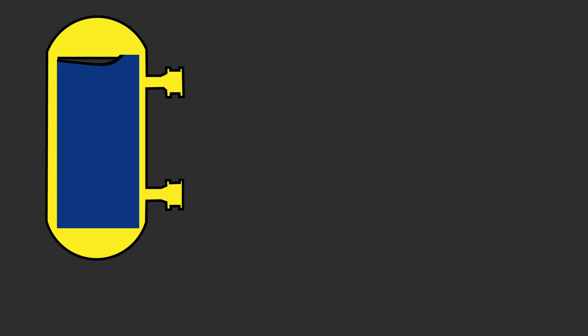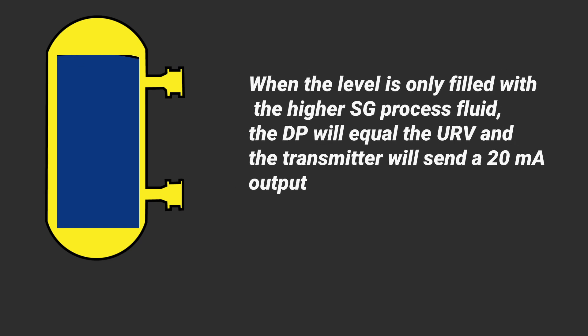Rule number three, when the level is only filled with the higher specific gravity process fluid, the DP or the differential pressure will equal the URV and the transmitter will output a 20 milliamp output.